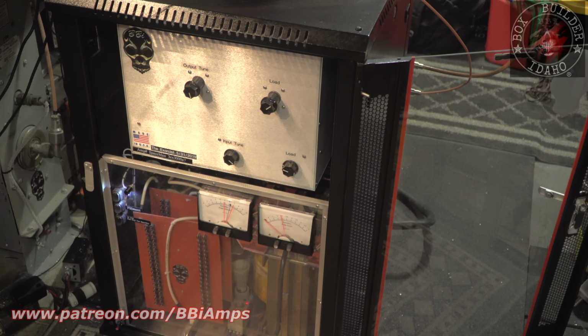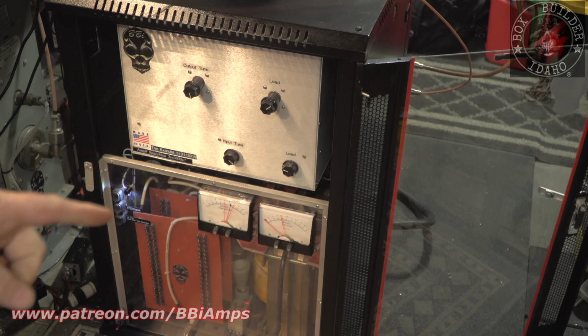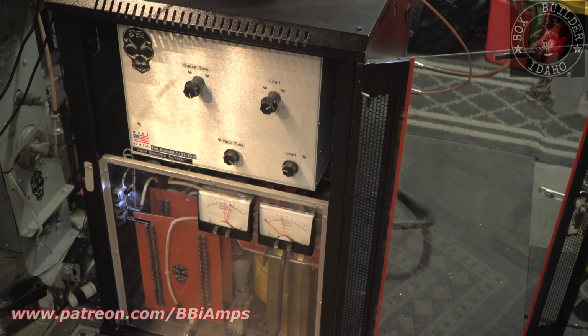Now that piece of tempered glass that the door is made out of, and this Lexan that's in the front, is what's keeping you from killing yourself. You cannot jam your hands in there in any way. All the switches, they work off of ground, but they only work off of DC ground. So the AC return and anything that could possibly even remotely electrocute you is hidden behind another relay or another contactor. Make sense? The switches cannot conduct high voltage in any way.